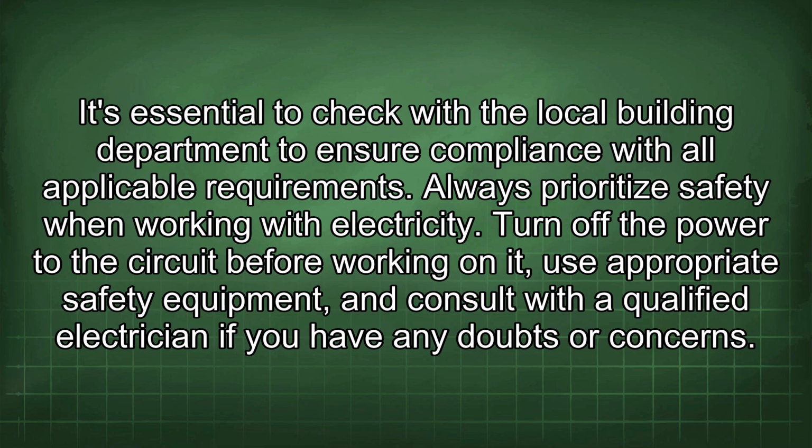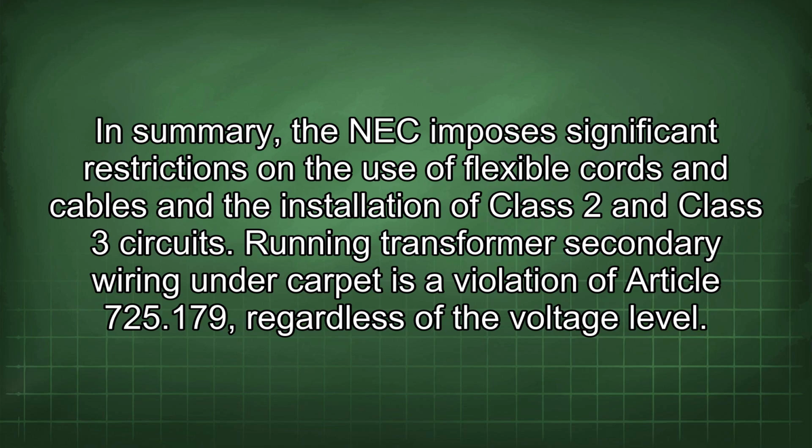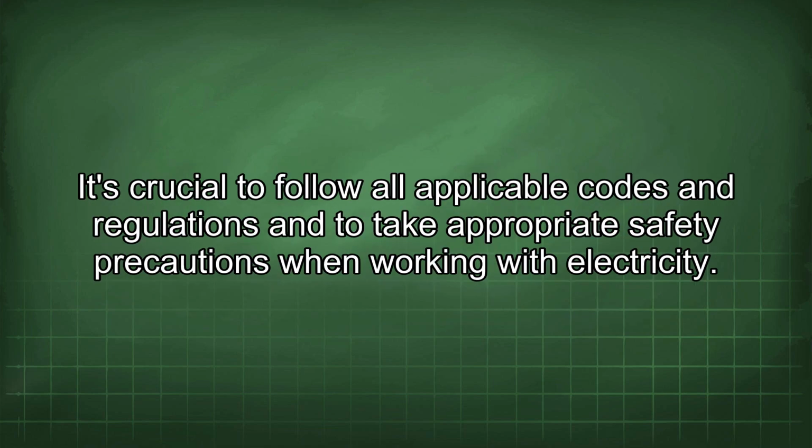Always prioritize safety when working with electricity. Turn off the power to the circuit before working on it, use appropriate safety equipment, and consult with a qualified electrician if you have any doubts or concerns. In summary, the NEC imposes significant restrictions on the use of flexible cords and cables and the installation of Class 2 and Class 3 circuits. Running transformer secondary wiring under carpet is a violation of Article 725.179, regardless of the voltage level. It's crucial to follow all applicable codes and regulations and to take appropriate safety precautions when working with electricity.